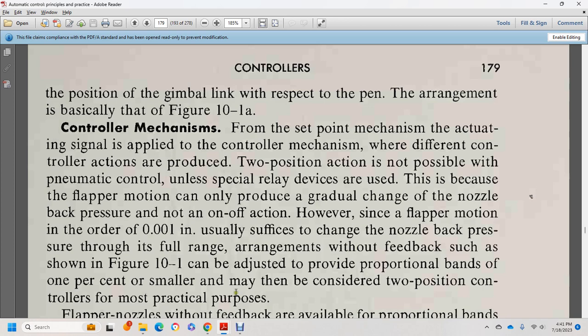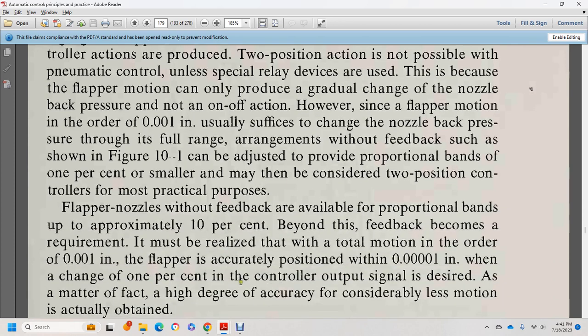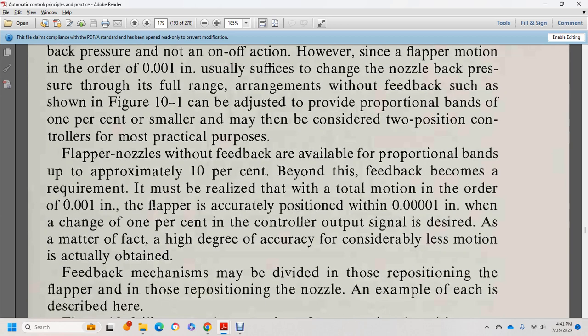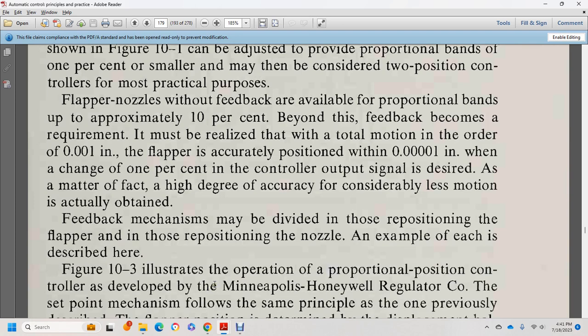Since the flapper motion is on the order of one-thousandth of an inch, we can supply the nozzle back pressure through the full range of arrangements. Without feedback, as shown in figure 10-1, proportional bands of 1% or smaller can be achieved. Without feedback, proportional bands of up to 10% can also be provided. The feedback mechanism may reposition the flapper or reposition the nozzle.